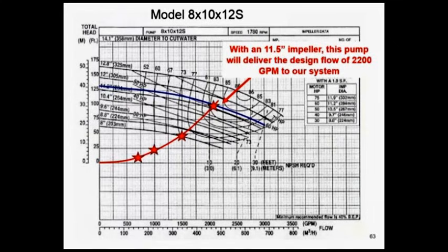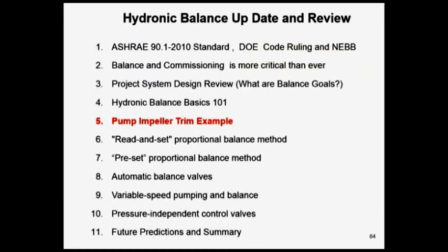If you did it accurately and you got exactly your requirement of 100 feet of head, you'll be at 2,200 GPM. If you overheaded your pump or you didn't have the right pump head, you will not be there, because that first law of thermo is going to apply, and wherever the system curve crosses the pump curve is where it's going to run. So you kind of got that in your head by now, I hope. Let's take some of these basic things we have learned and look at pump impeller trimming, why it might be important, how you would do it, and how it fits into ASHRAE 90.1 and balance. See if we can bring some of this together for you now.